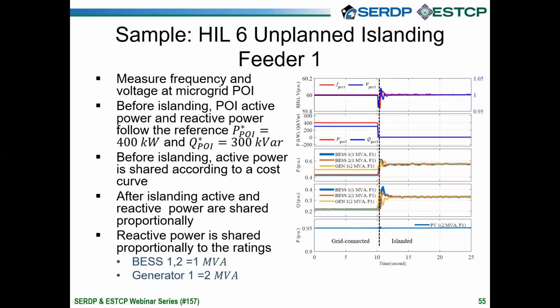The next example, and in the interest of time, I'm jumping ahead, shows what happens if we have an unplanned islanding on feeder 1. So what happens here is that all of a sudden we have to disconnect from the main grid, and we have to stabilize the microgrid rather quickly. So you see at around 10 seconds from the test beginning, we have an unexpected disconnect event, in which case the real and reactive power coming from the main grid all of a sudden drops to 0. That's on the second diagram.